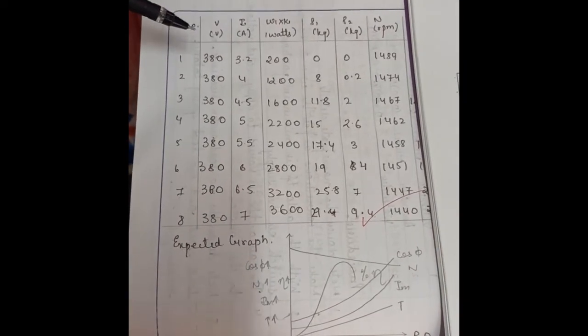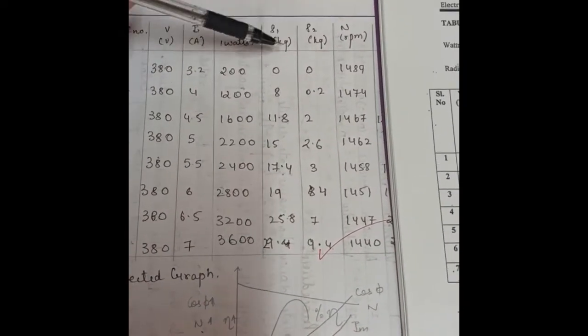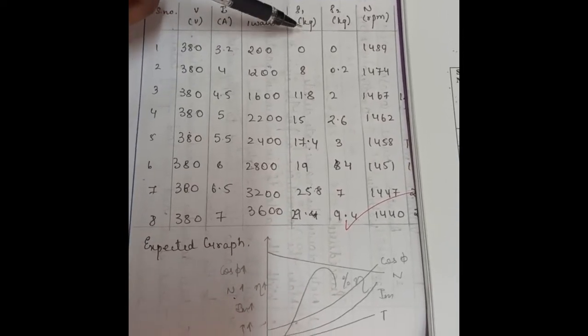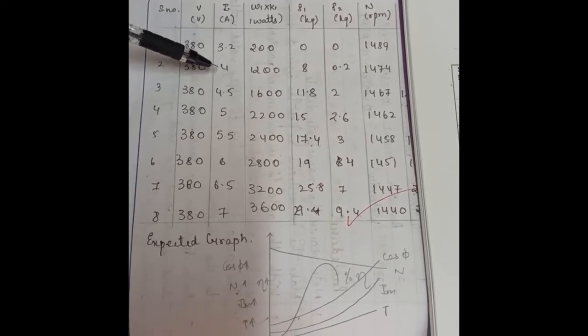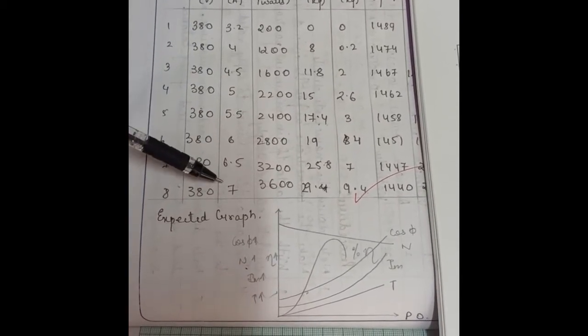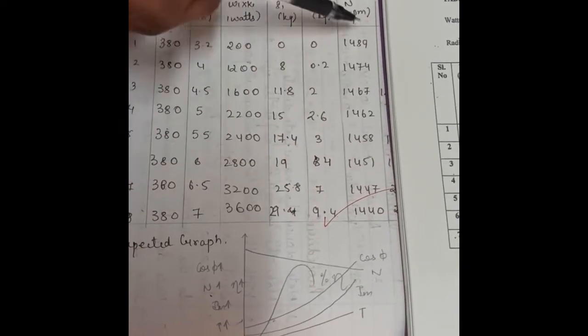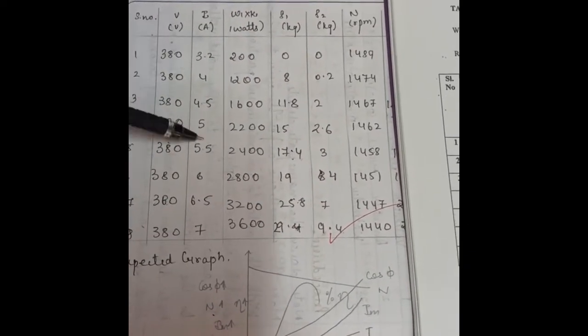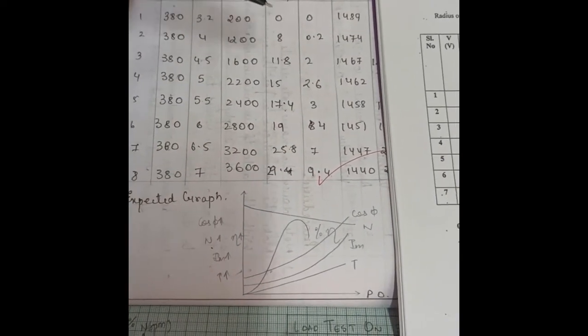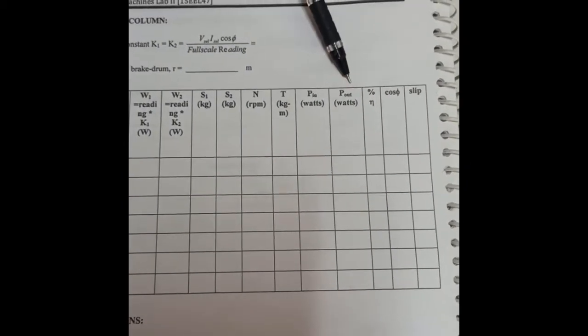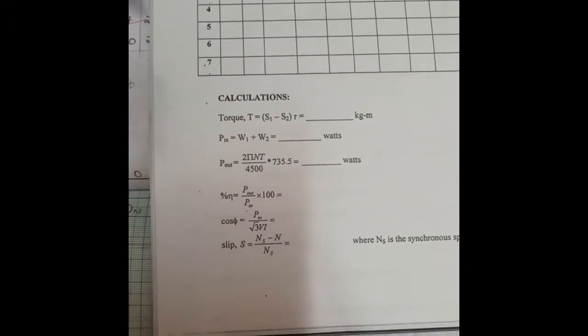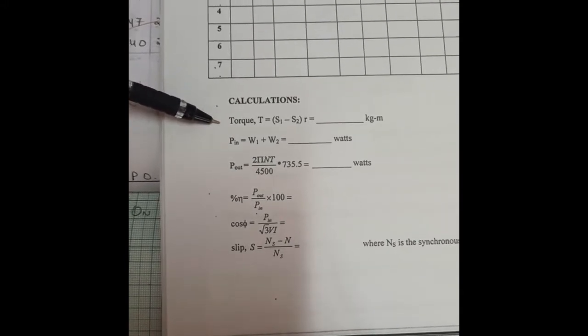So by conducting the experiment, we will note down voltage, current, two wattmeter readings W1, W2, and then the load readings S1 and S2 in each step. So we can increment the current in steps of 0.5 amperes and take down the readings only up to 7 amperes. So you can note the corresponding readings at each loading condition. Once these readings are noted, to complete the calculations we have to find a few more parameters, that is torque, input power, output power, efficiency, and then power factor and slip. Now there is a set of formulae which has to be used in order to calculate these values.